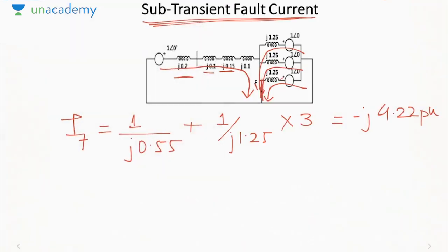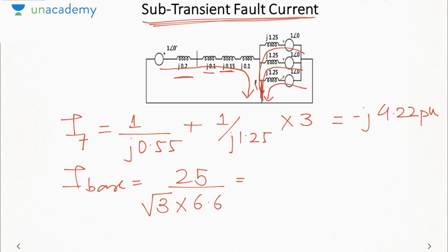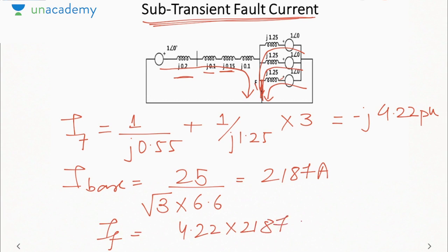To calculate the actual value, we will have to calculate the base current in region 3, which is 25 MVA by root 3 into 6.6. So this base current will come out to be 2187 ampere. So what will be the fault current? That is 4.22 into 2187, which is equal to 9229 ampere. That will be your fault current, or the subtransient current going into the fault.